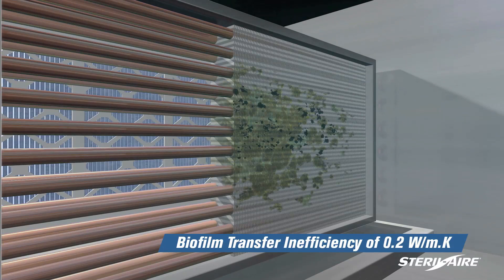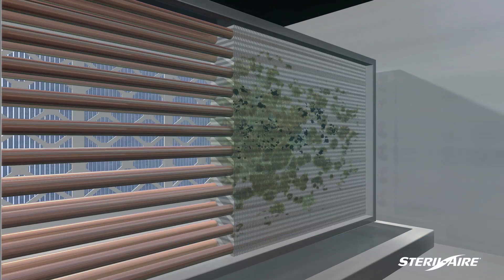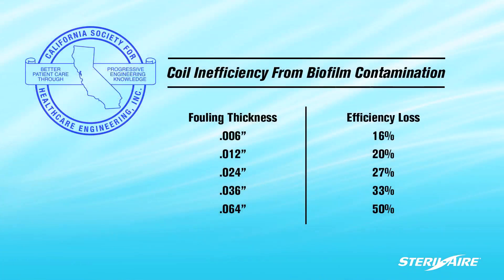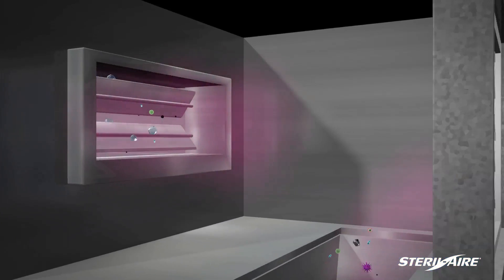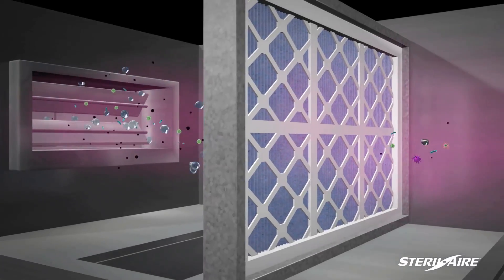or approximately 1,000 times less efficient. According to the California Society for Healthcare Engineering, it only requires a 0.15 millimeter fouling on the coil fins, 0.006 of an inch, to reduce the coil's efficiency by 16%.